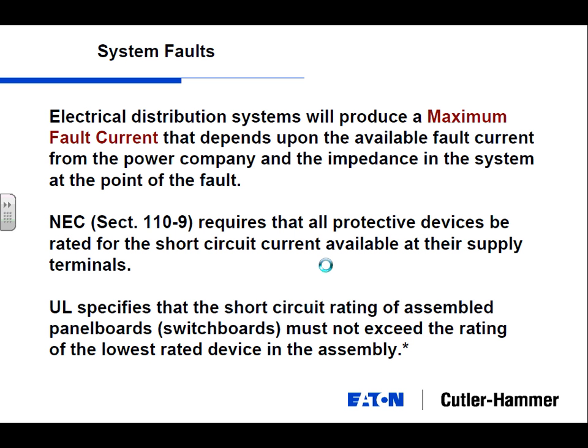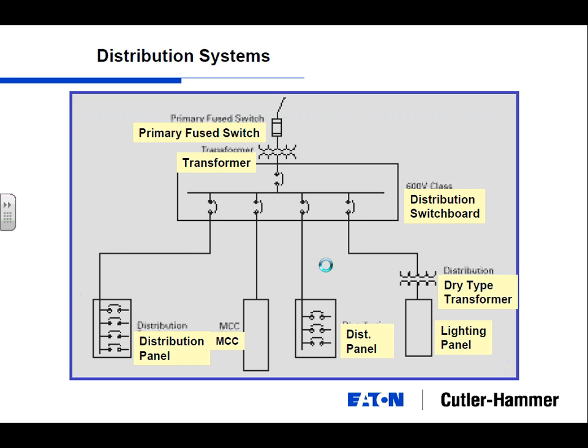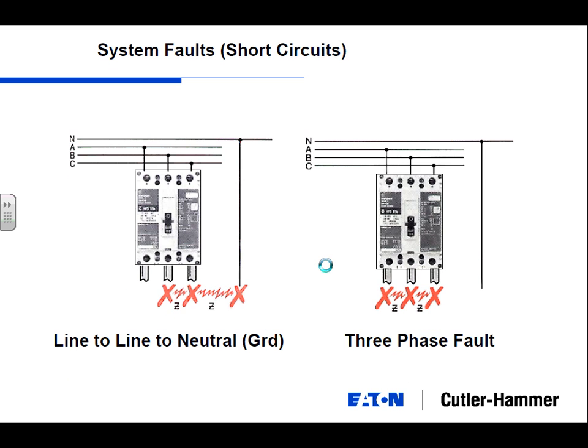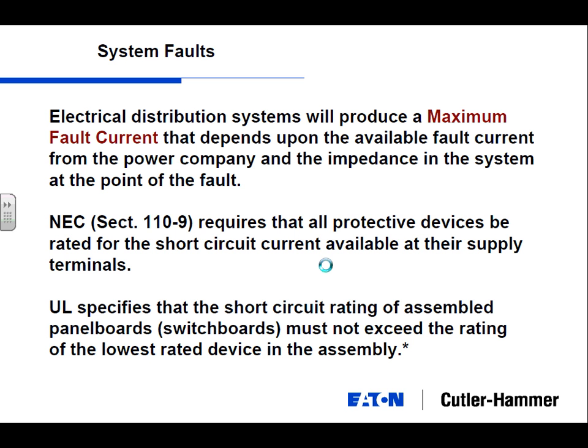The engineer, or the engineer of record, will have to do a short circuit study, basically what they call it. And the short circuit study will then factor in the calculations of the impedances of all the cables, and you can look at an entire distribution system like this and look at all those different points and tell you what the fault current is at all those different points of the distribution system. That's required by NEC.